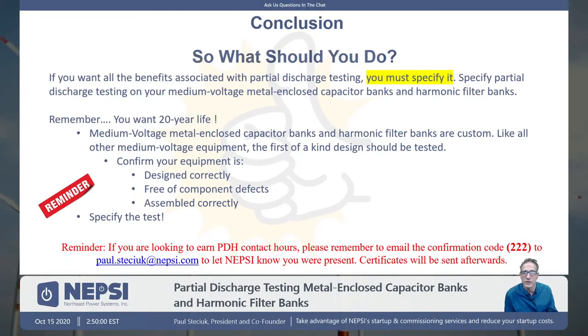So in conclusion, remember, medium voltage metal-enclosed cap banks and filter banks are custom. If you want a 20-year life, specify partial discharge testing. You've got to specify the test if you want to make sure you're buying equipment that's of high quality and that will last 20 years.